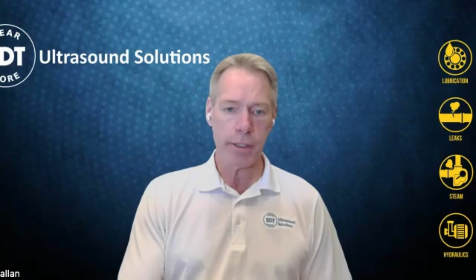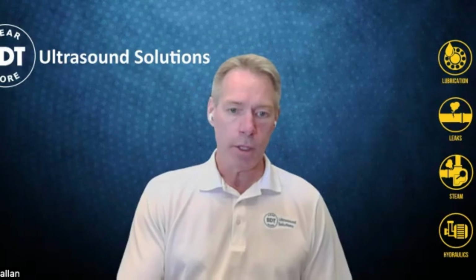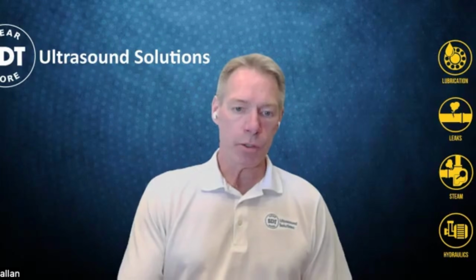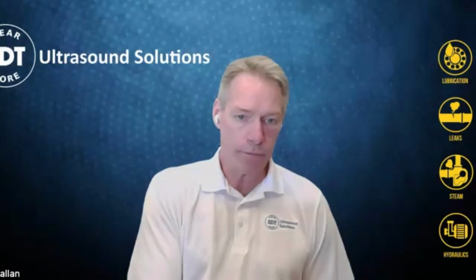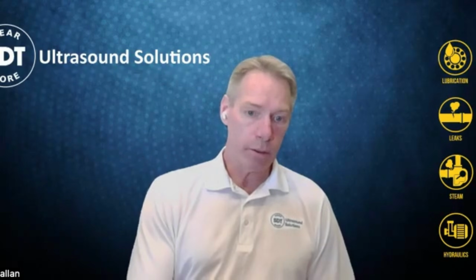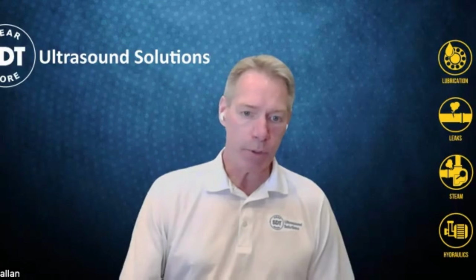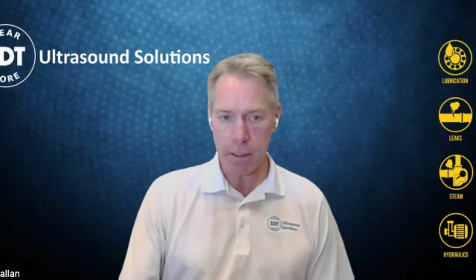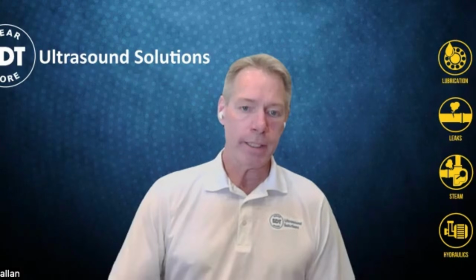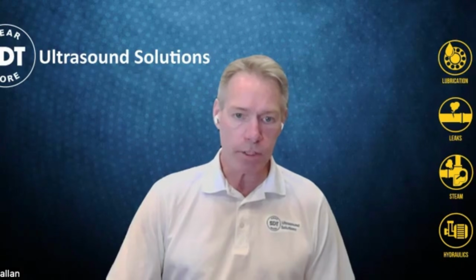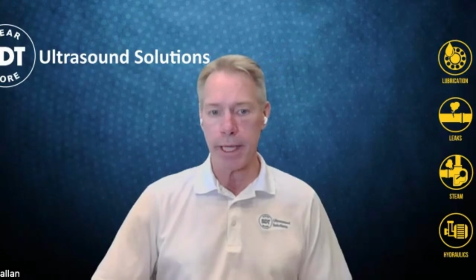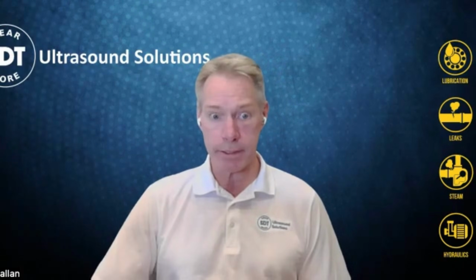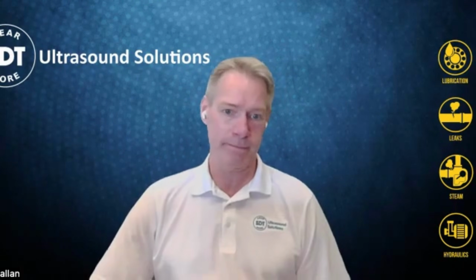The advantage here now is that with ultrasound, we see that problem much sooner. So if we have a stage 1 or a stage 2 failure in a bearing, which isn't going to get picked up with vibration analysis easily, now we can plug that in and see if it's an inner race or an outer race failure. So we're doing similar diagnostics with ultrasound, and the data is being collected by your lube tech.